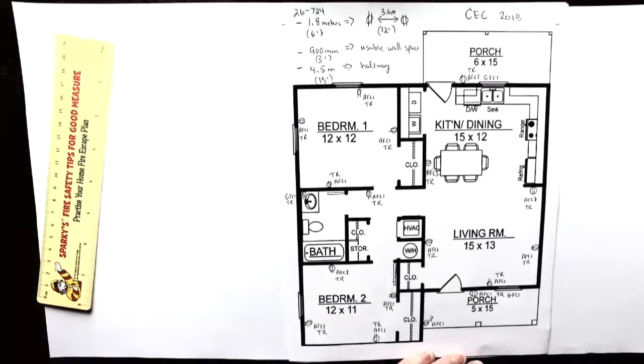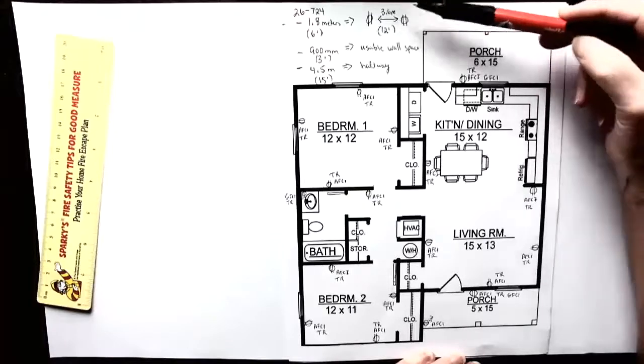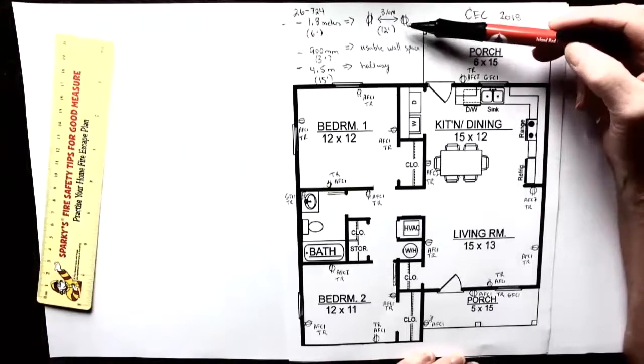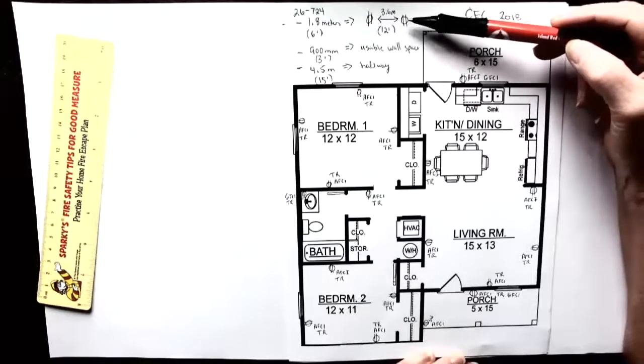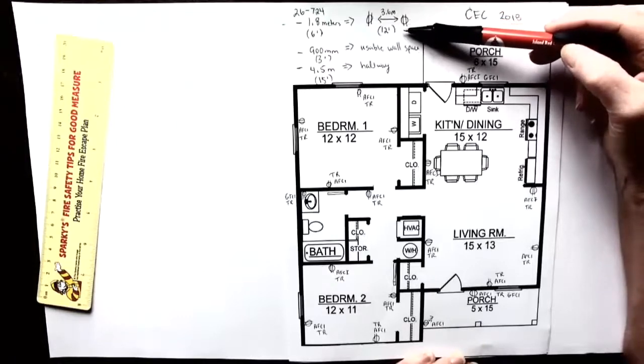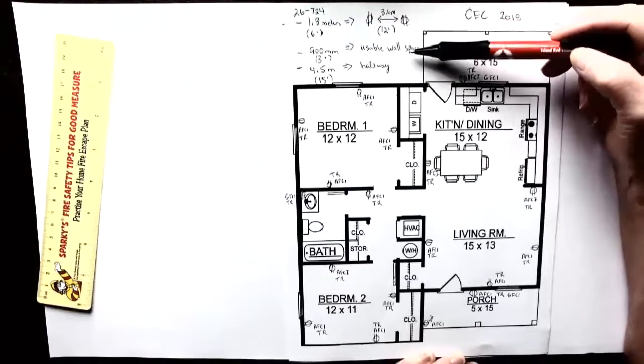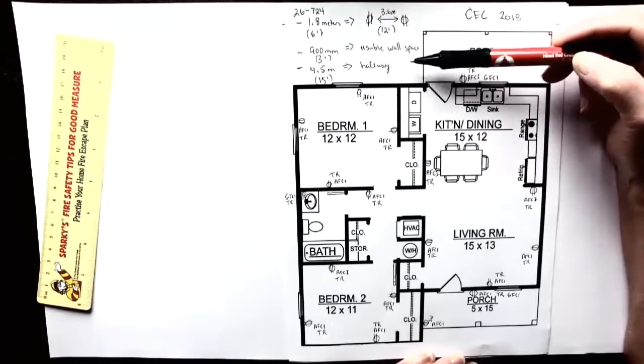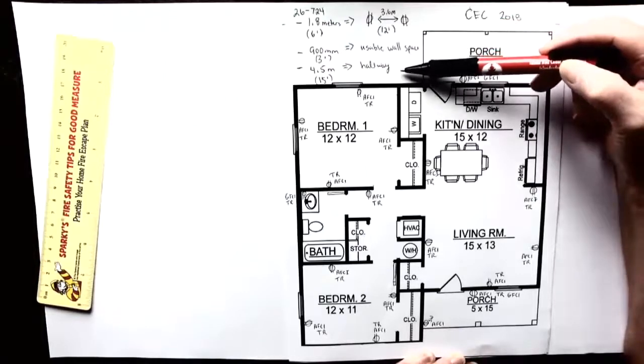If we just reviewed 26724, it says that no point along the wall can be more than 1.8 meters or six feet from a receptacle. That means that the two receptacles can be 3.6 meters apart or 12 feet apart. A usable wall space is considered anything that's 900 millimeters or more. And in a hallway, we need a receptacle, at least one receptacle so that no point along the wall is more than 4.5 meters from a receptacle.